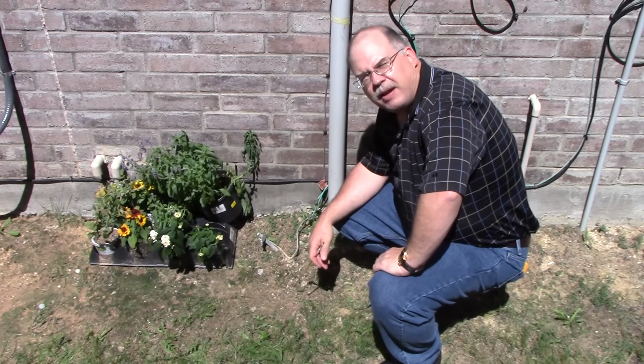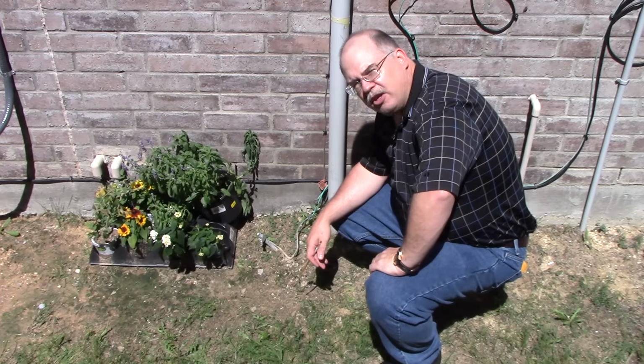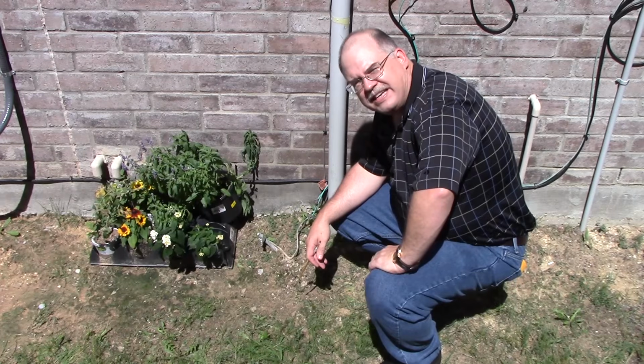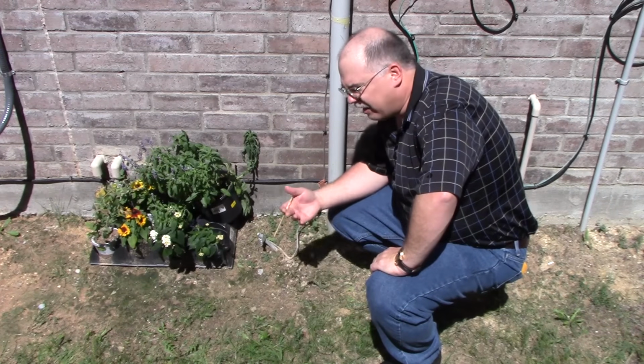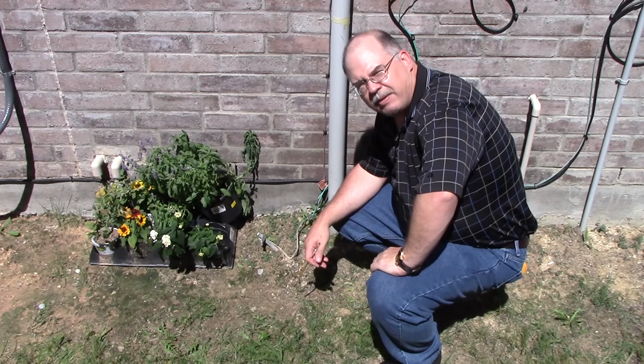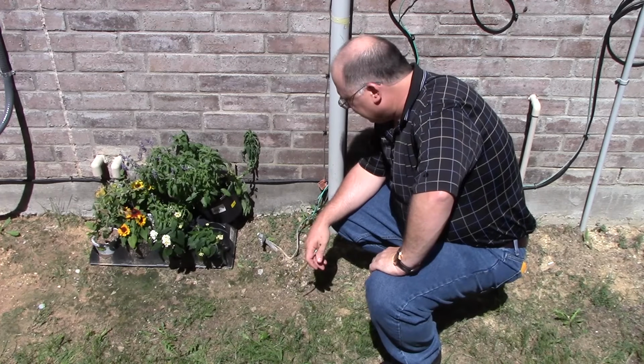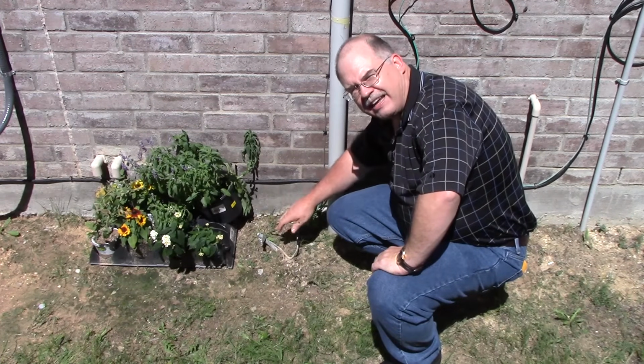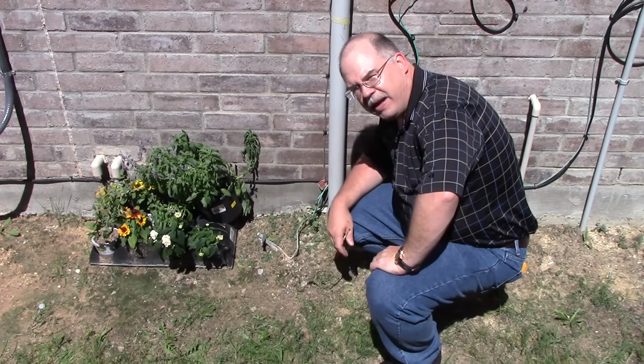Since it's not required, I'm not too often concerned about it. If I was a municipal inspector, I would make them drive it all the way down, flush with the earth, or below. The code actually says below the frost line, but I really want to get it below the surface. They can cup out the dirt, if you will, so I can actually see it on inspection, and then they can cover it back up.